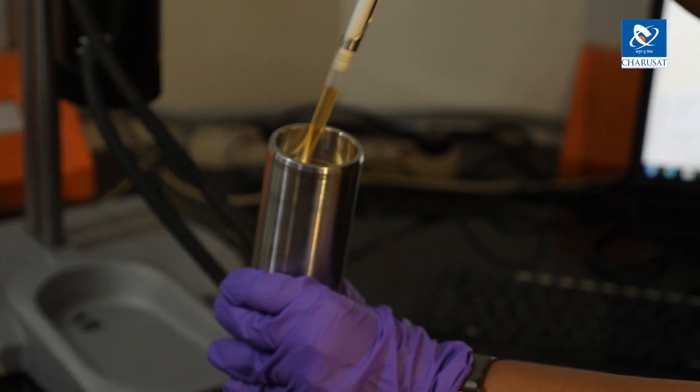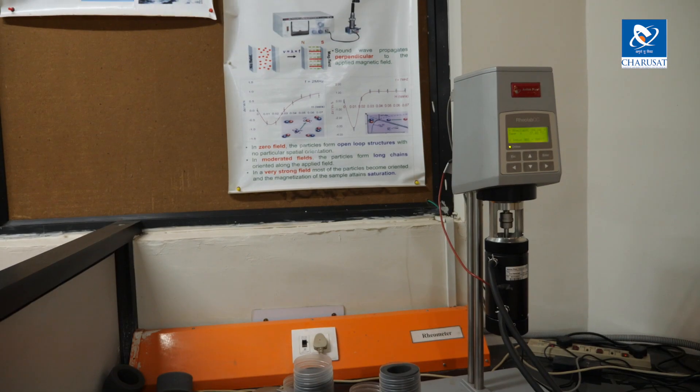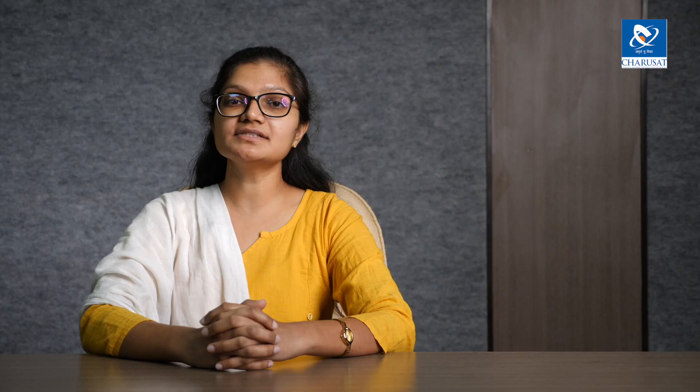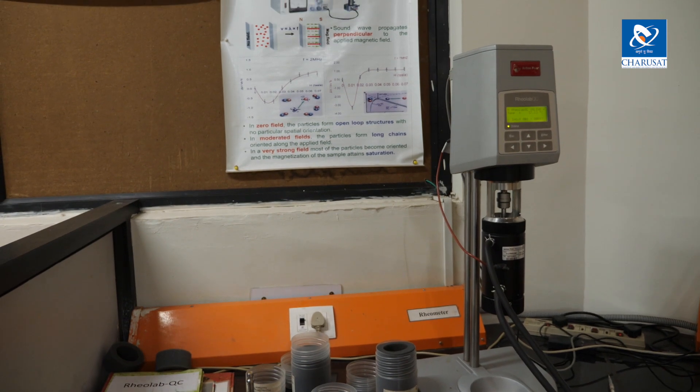This rheometer can measure viscosity in a vast range, starting from liquids having viscosity even less than water up to semi-solid liquids — everything in between these two extremes can be measured. The RheoLab QC is a rotational rheometer; it can be operated in standalone mode or software controlled. There are two measurement geometries: concentric cylinder and double gap. Quick measurements are also possible, for example a single point check over a flow curve or a yield stress determination.